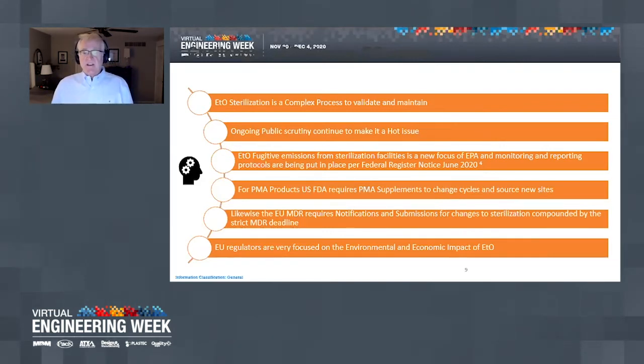in the US. EPA is continuing to be under pressure from the public to implement and enforce zero emissions. Fugitive emissions sounds like something out of a prison movie, and as it suggests, it refers to the EO gas and residuals that escape the chamber during the process and are released into the ambient air that we breathe. EPA has issued a Federal Register notice to outline the monitoring and reporting on this issue now in response to this, and we're in this sort of reporting period. They haven't made their decision on the limits, but they're collecting data.